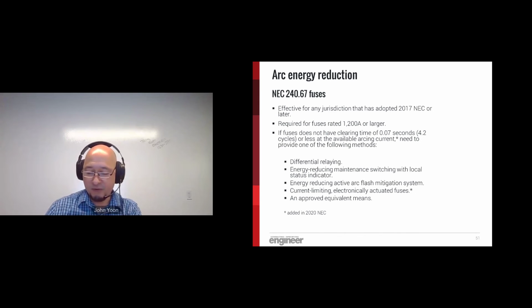If you remember in those previous slides with the time current curves, both breakers and fuses react quickly to bolted faults in the instantaneous region. Remember that dogleg curve, and that dogleg in the half to one cycle range of a molded case circuit breaker? However, the magnitude of current associated with arc flash faults is typically only a third to half of the magnitude of a full-on bolted fault. This puts us in a different place on the time current curve.